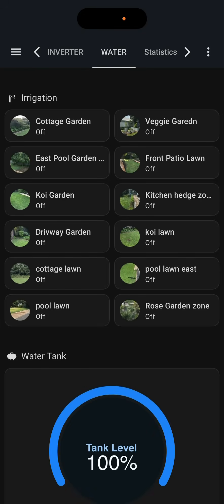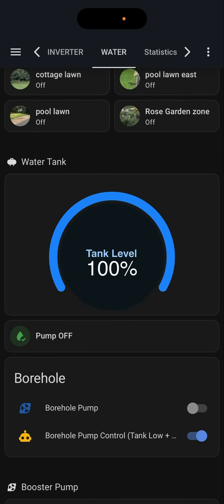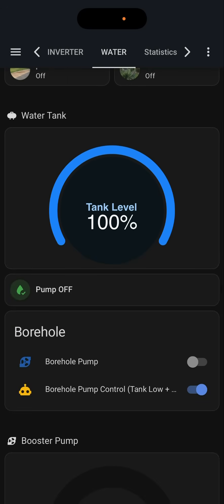On this particular installation, we've got our water systems also incorporated, which is really nice. All the irrigation zones are here. We've got a water tank with a level indicator and a borehole pump with its controls, all automated. They work when the tank level drops down — it'll automatically switch the pump on. We're able to prioritise when this pump runs; the borehole pump will only come on when the battery charge is above 50%, and every day at 3 o'clock it triggers a pump to top the tanks up so there's enough water for the night.